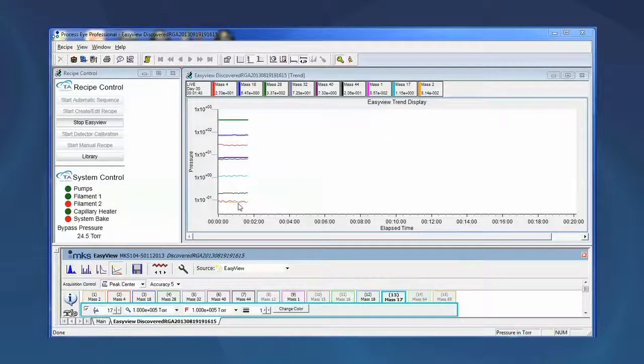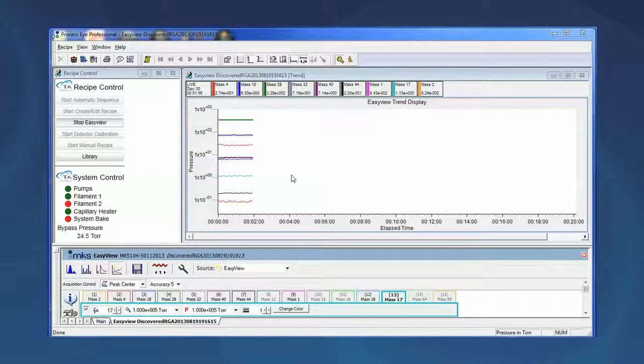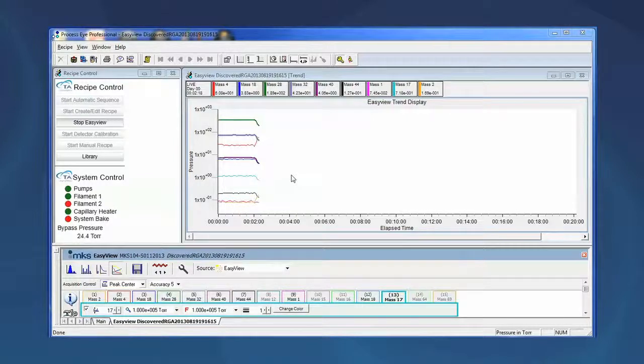Tracking these gases will give us a feel for how well our detector is responding. I'm closing the furnace now and I expect the relative concentrations of the gases to change dramatically with respect to the concentration of helium. You will see the change almost immediately as the furnace closes. There will be a very quick shift in the baselines as the atmospheric gas reduces in concentration. Helium will begin to trend upward. Notice the red line is increasing as is the orange line down toward the bottom of the graph. There is now no doubt that mass 2 in this case represents doubly ionized helium and not hydrogen gas.